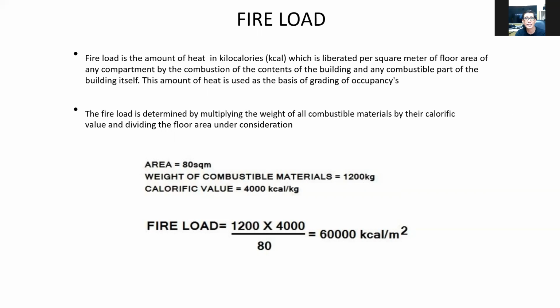So you total all the actual weight and you refer to a calorific value table. Okay, so you can get that calorific value table on the internet. You can download that. Then you can summarize what is the equivalent of 1,000 kilogram into calorific value, which is 4,000 kcal per kilogram. So now if you multiply the fire load of 1,200 times the calorific value divided by the number of square meters, you have 60,000 calorific value per square meter. That is the actual fire load of your building, of the room.